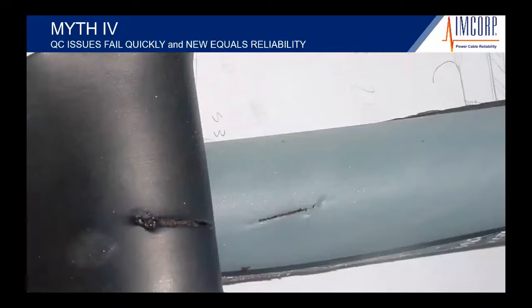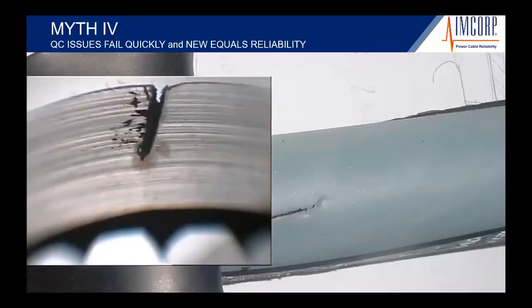Here's a 30-year-old cable that we did a cable life extension program on. This was showing partial discharge. We took a look at this cable and we did a dissection of it. The first time we looked at it, we saw the gash immediately, right? It was showing partial discharge on our testing system. A closer look, there was a cut in the insulation that was well over half the distance of the insulation itself, but it hadn't gone to failure.